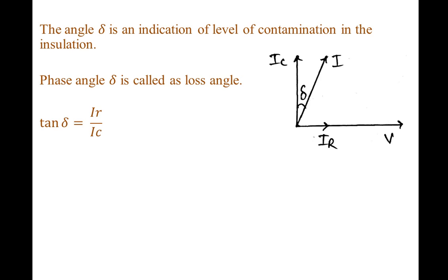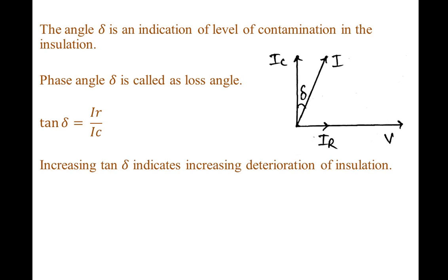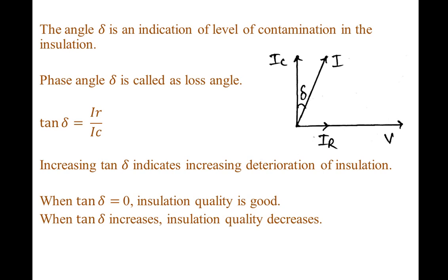Tan delta is equal to the ratio of resistive current and the capacitive current. Increasing tan delta indicates increasing deterioration of insulation. When tan delta is equal to 0, insulation quality is good. When tan delta increases, insulation quality decreases.